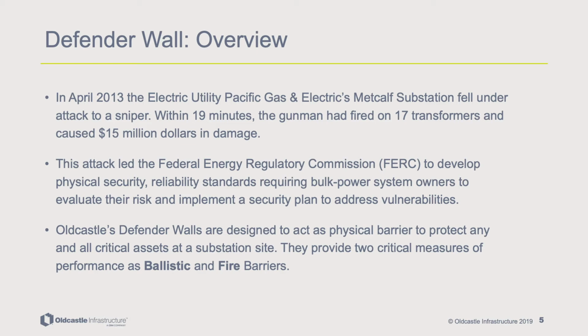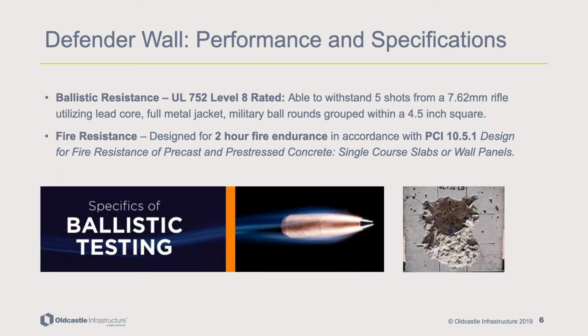Oldcastle's Defender walls are designed to act as physical barriers to protect any and all critical assets at a substation site. They provide two critical measures of performance as ballistic and fire barriers. Defender walls maintain a UL 752 Level 8 rated ballistic resistance. These walls are able to withstand 5 shots from a 7.62mm rifle utilizing lead core, full metal jacket, and military ball rounds grouped within a 4.5-inch square. Oldcastle's Defender walls are also rated with a 2-hour fire endurance in accordance with PCI 10.5.1.